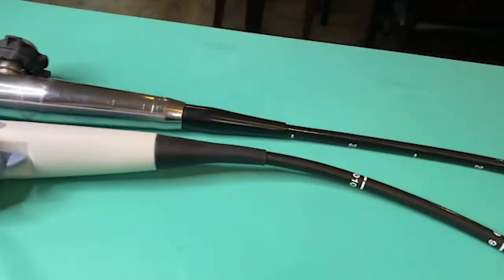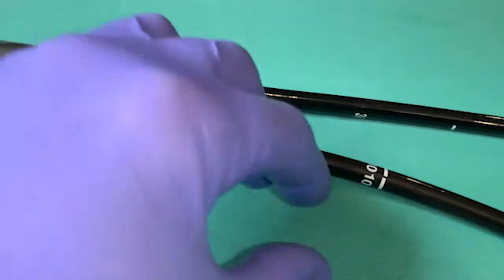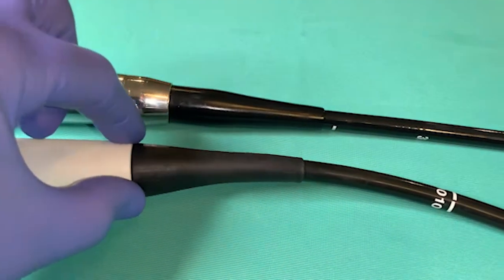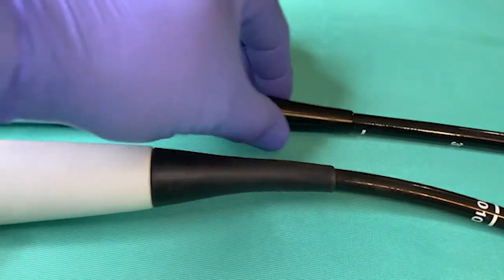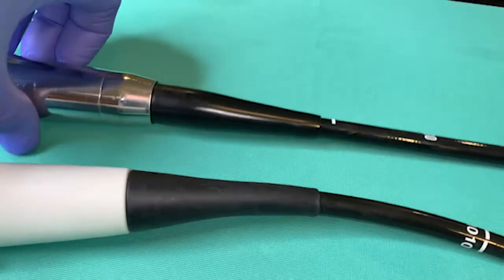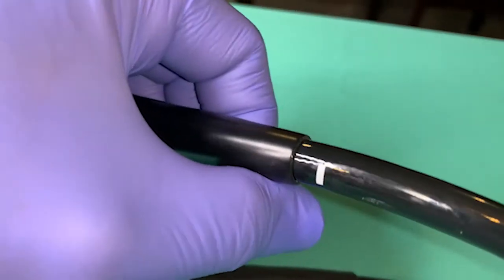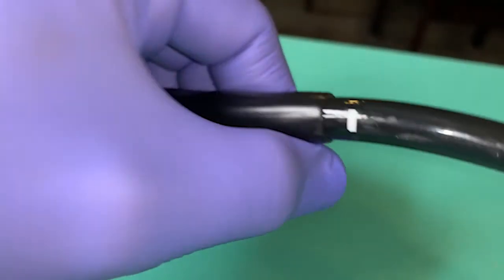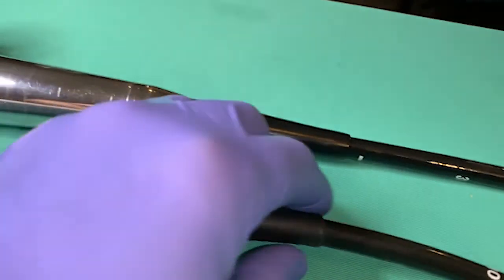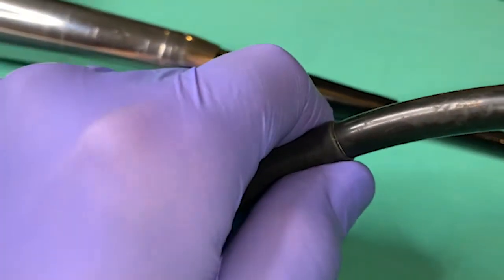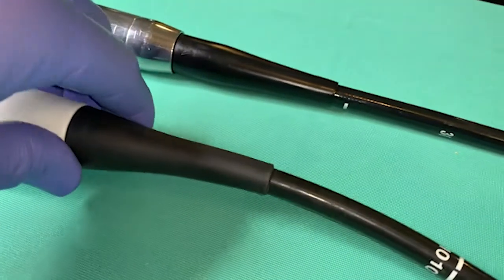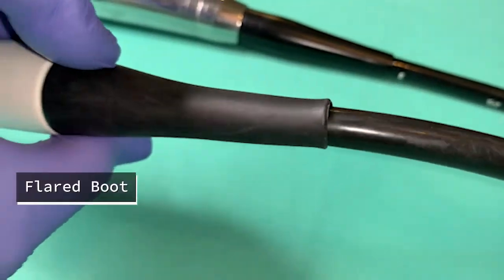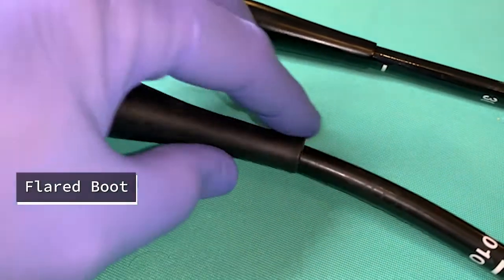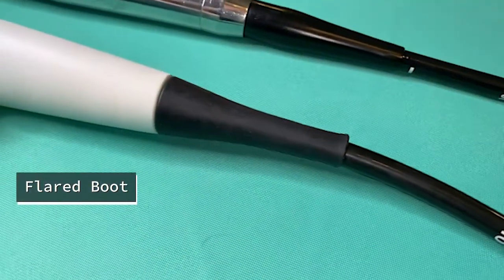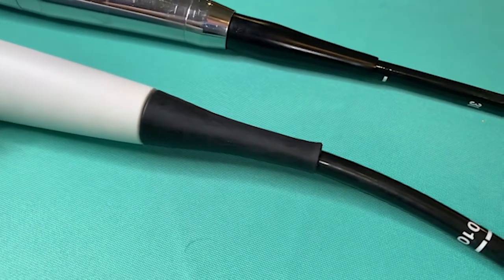The boot or insertion tube strain relief is located where the insertion tube connects to the control body. The snugness of the boot may differ by probe model based on OEM design, but it should not appear flared out or should not have any external damage such as tears or cuts. This area is fluid resistant but not fluid proof. It cannot be submerged as fluid can wick up inside of the boot and flood the internals of the probe.